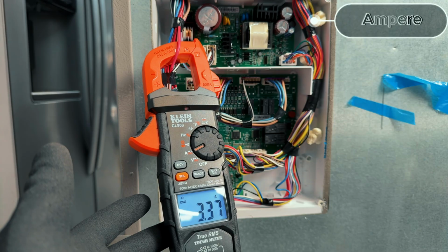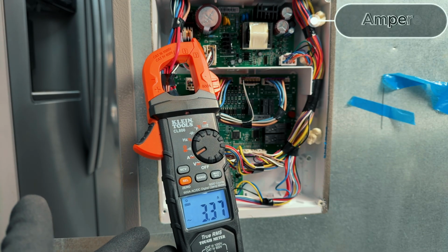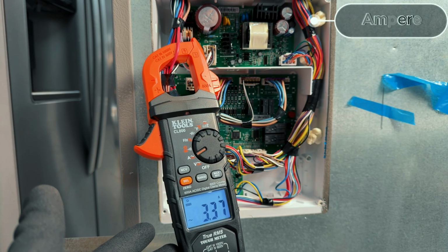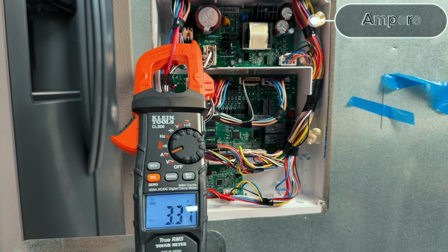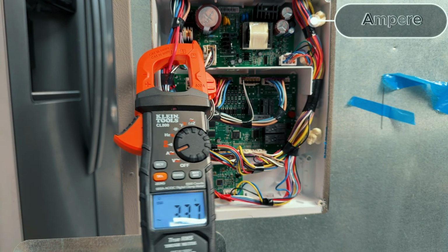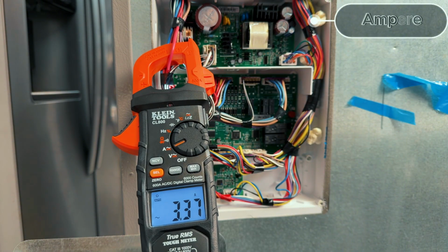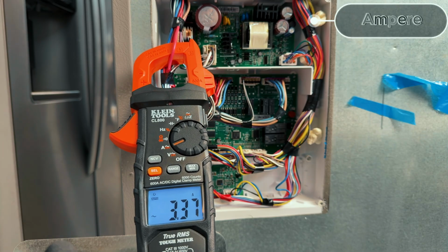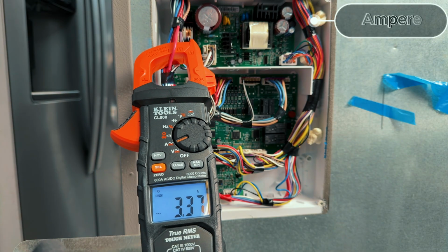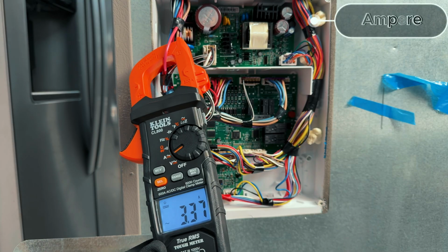So if I have a visual indication of a defrost heater failure, there might be something else going on because clearly my heater is not the issue. So there's got to be something going on with the activation of that heater itself. And if you're not sure what amperage you should have when you're checking a load, you can always check the tech sheets or schematics to understand what the wattage potential, resistance value, voltage, and everything like that goes to that load. And you should be able to use Ohm's law to be able to determine what kind of amp draw that load is going to be pulling. And on this one, of course, we're checking good.